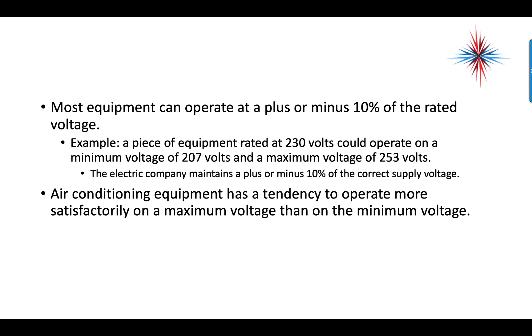Air conditioning equipment has a tendency to operate more satisfactorily on the maximum voltage than on the minimum voltage. In recent years, I have been seeing more and more power supplies hitting close to the 240–245-volt level from the utilities rather than the 230–207-volt range. The utilities are actually starting to provide a higher voltage to buildings to prevent voltage drop when everything is running at one time.